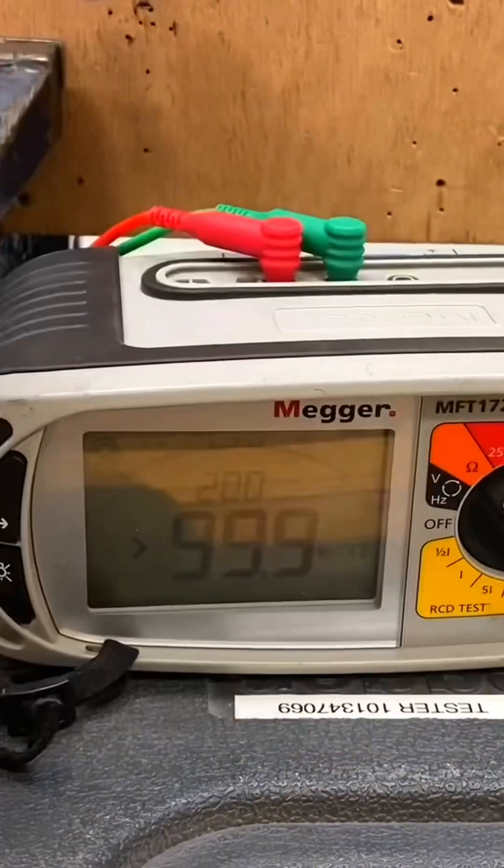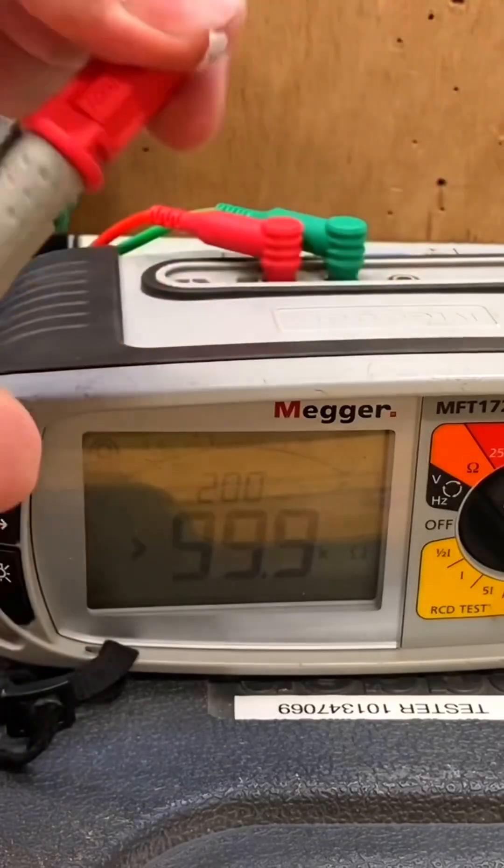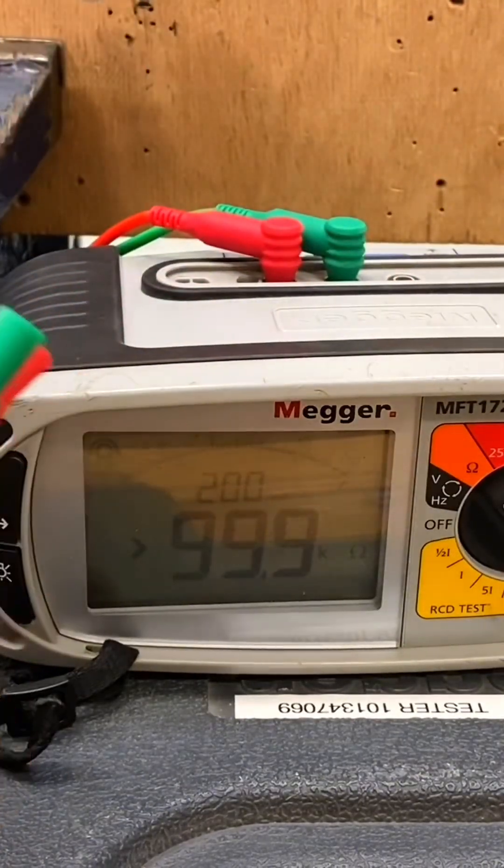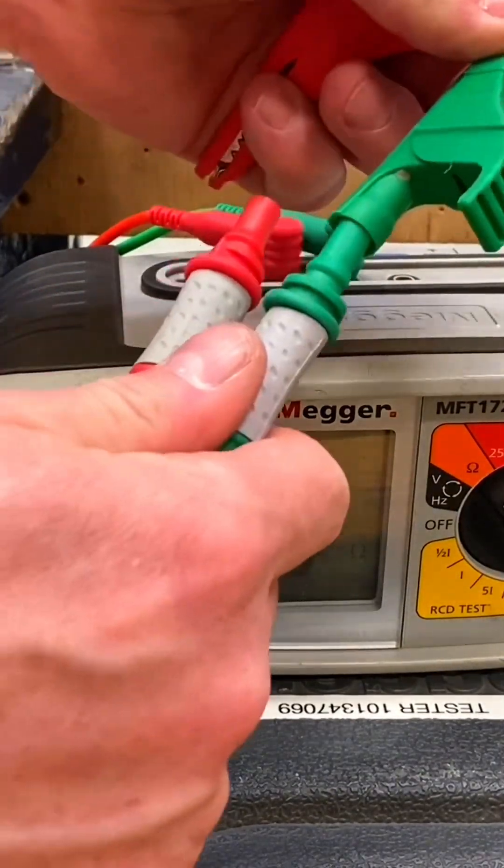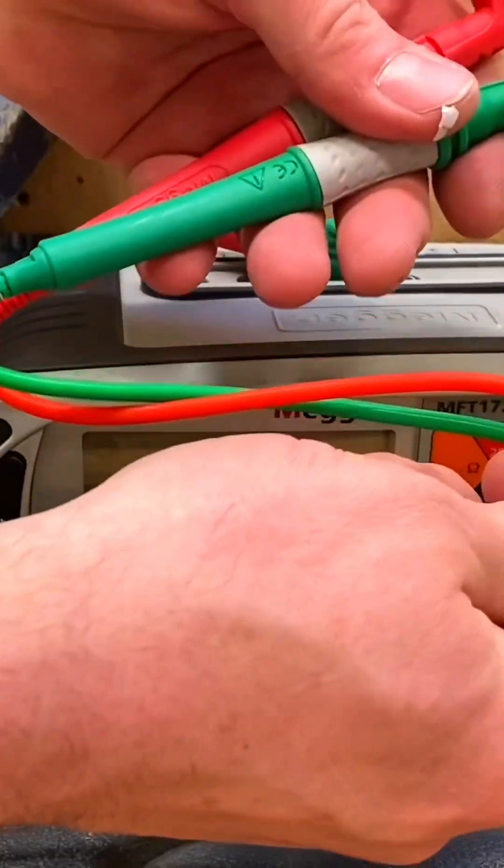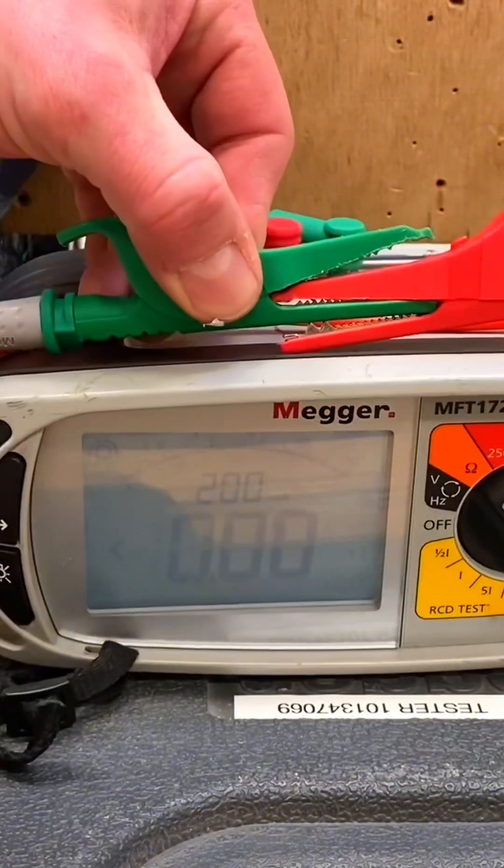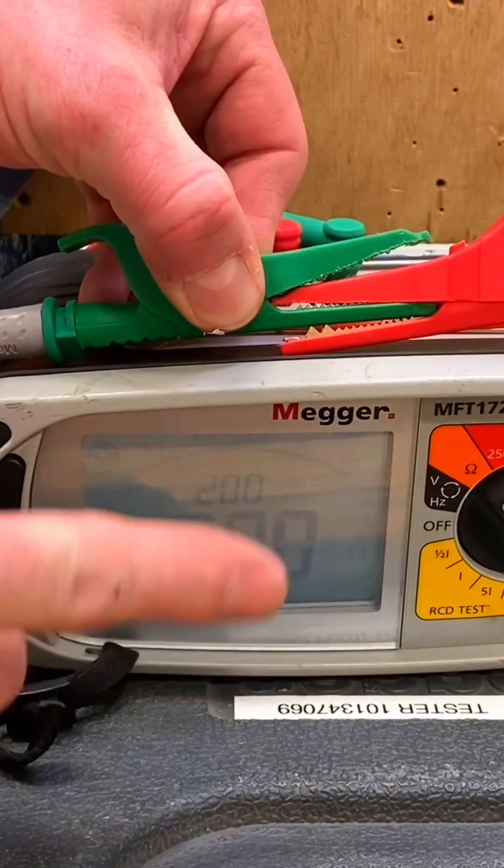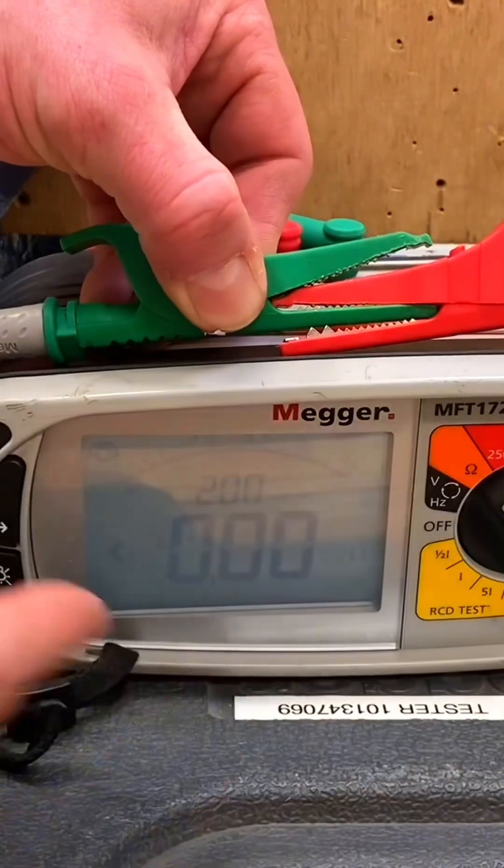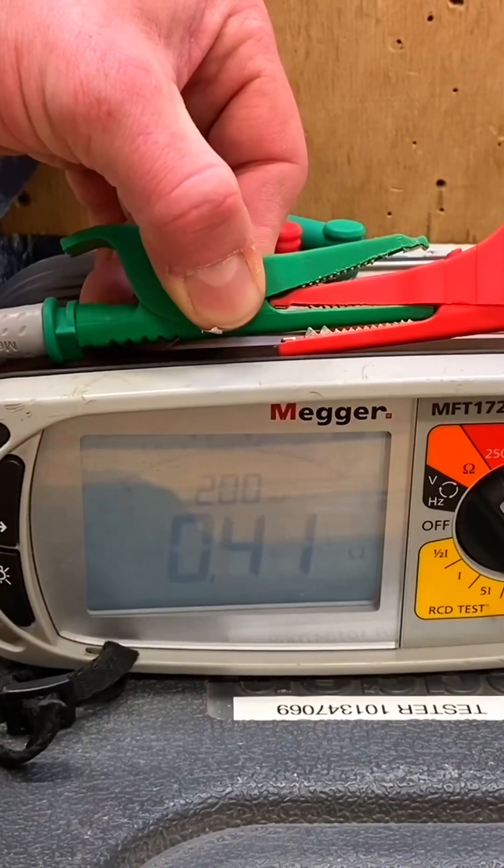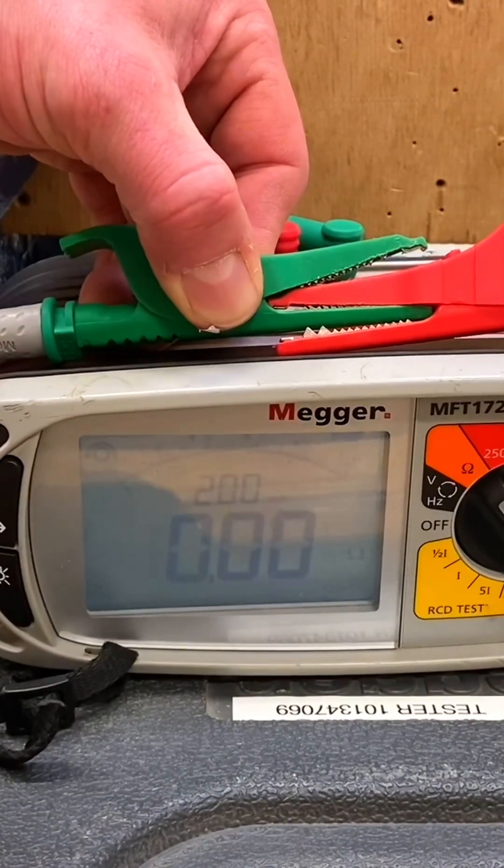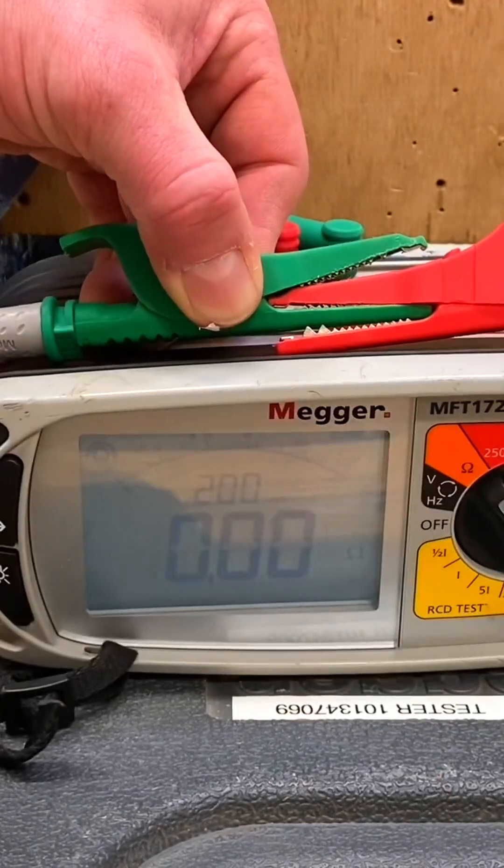I'm going to change to crocodile clips to remove the resistance of the leads. Remember, the leads have copper in them and will offer resistance in circuit. Maximum surface area to maximum surface area - flashing zero means it's below zero. Press the test button once, then again, and we've got a stationary zero. We've removed the resistance of these leads and we're ready to do the test.